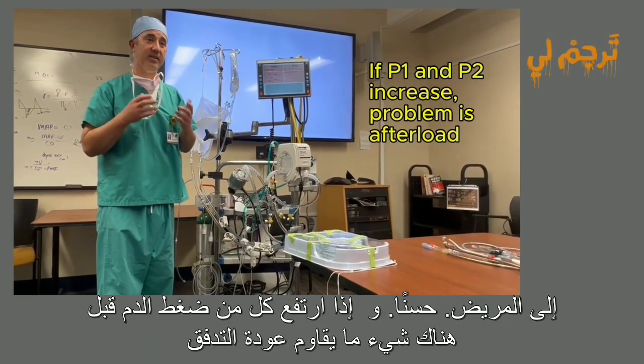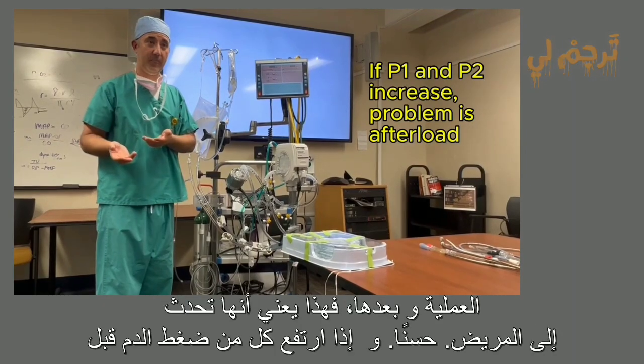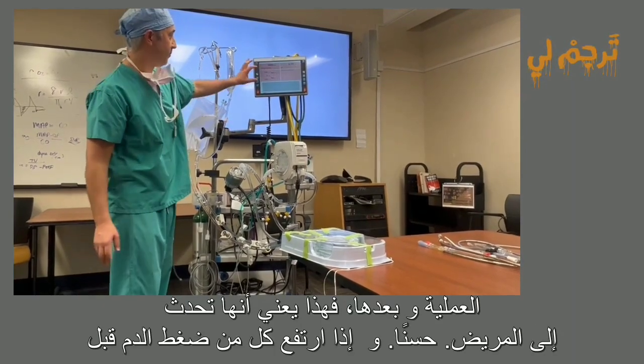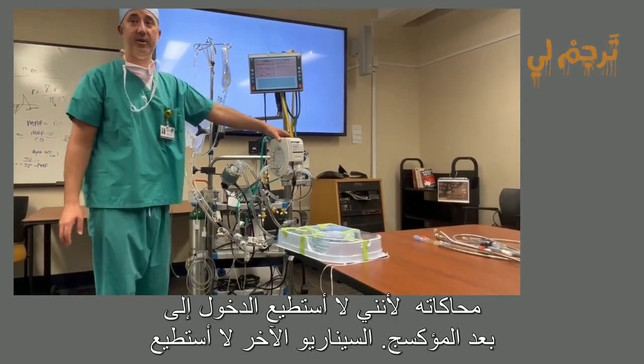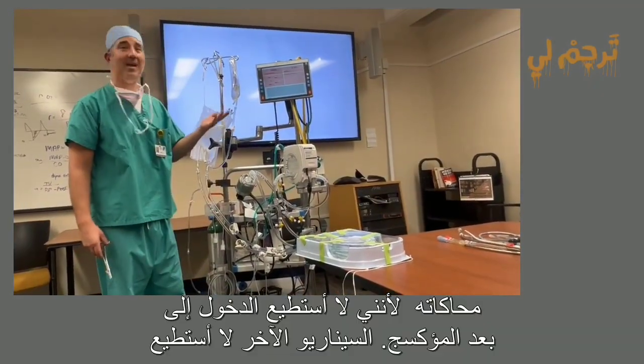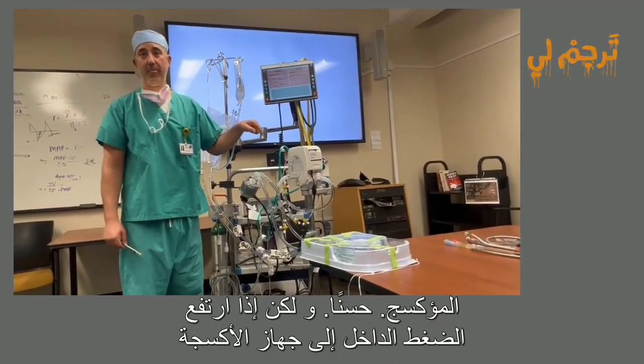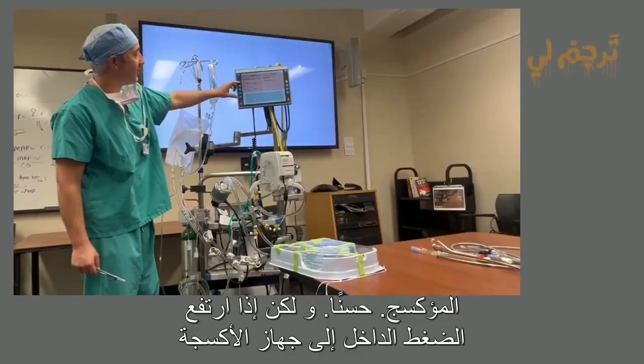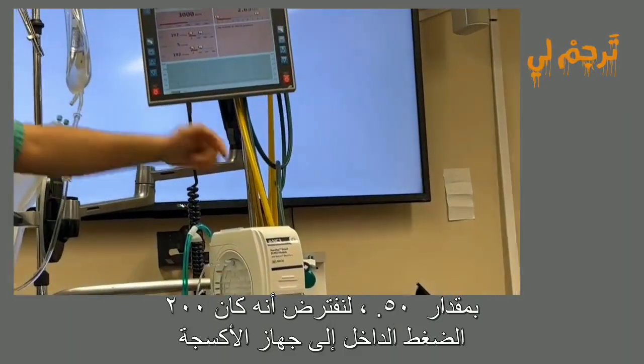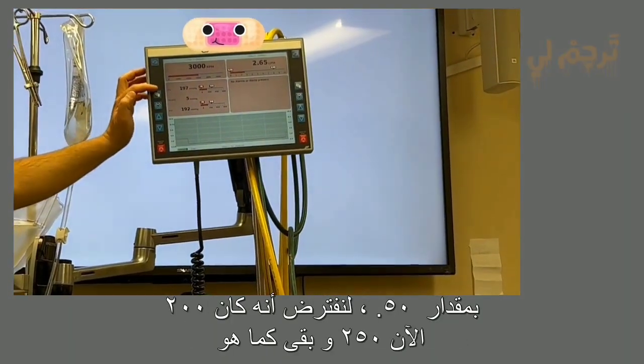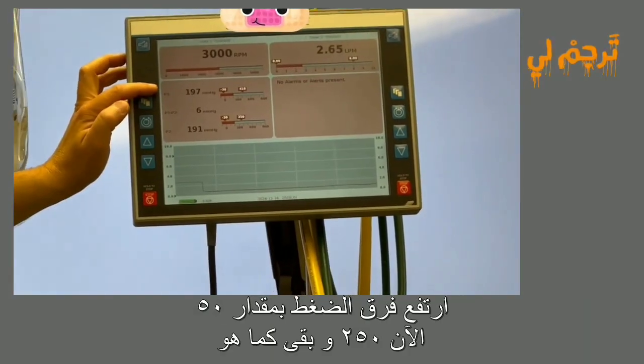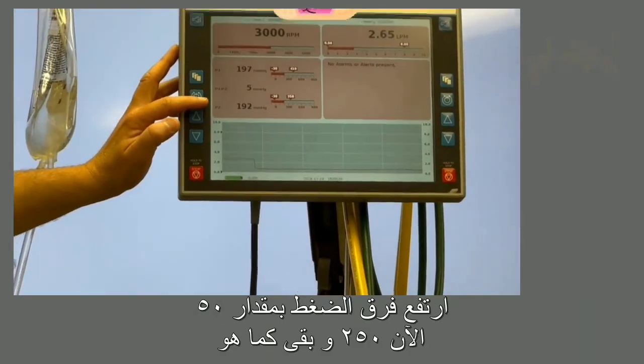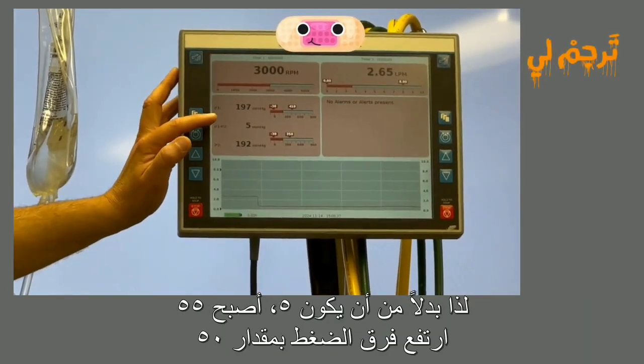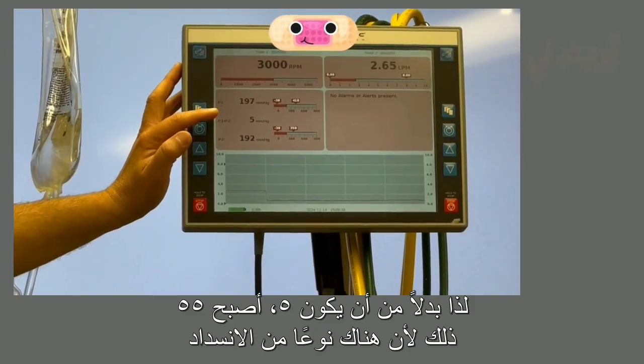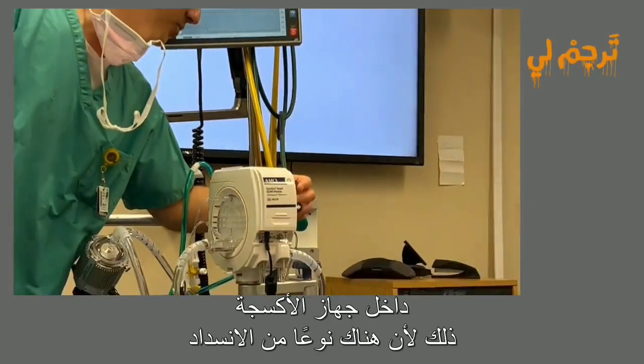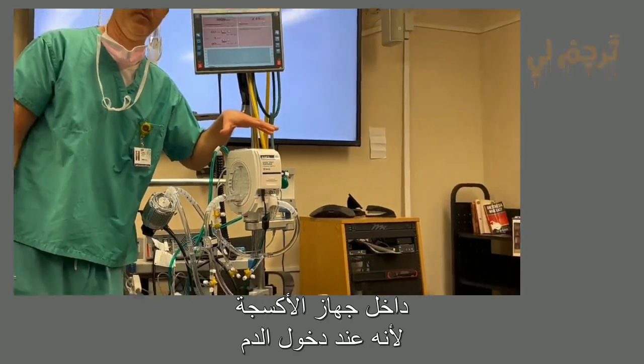There's something resisting the flow going back into the patient. All right. And then if it's pre and post both going up, it's after the oxygenator. The other scenario I can't mimic because I can't get inside the oxygenator. But if the pressure going into the oxygenator goes up by 50, so let's just say this was 200, now it's 250, and this stays the same, my delta P just increased by 50. So instead of being 5, it's 55. That's because there's some sort of obstruction inside the oxygenator.